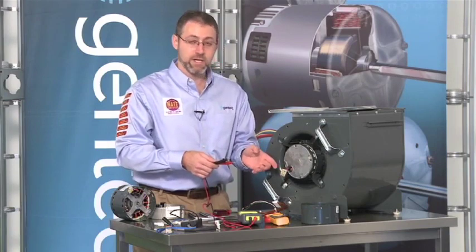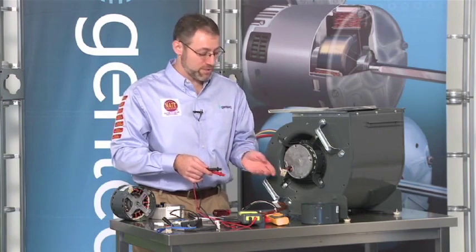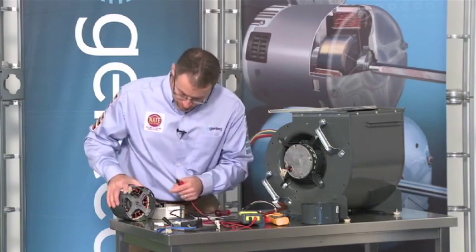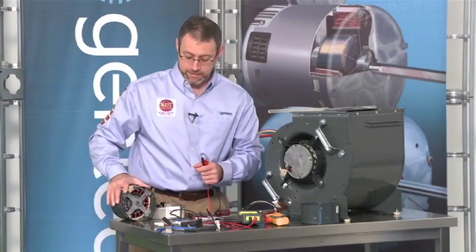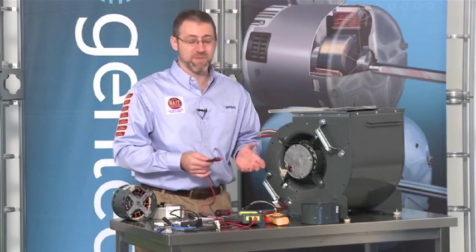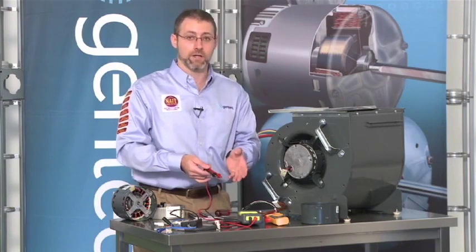If we're reading infinity on all three of our leads, that one check is a good check. That motor passes that check. If any of those readings was less than infinity, really less than 100,000 ohms, then there's some continuity between the windings of the motor and ground, and that would indicate a failed motor, no sense in even doing the second check. It's been my experience that most motors either read infinity or zero on the meter.